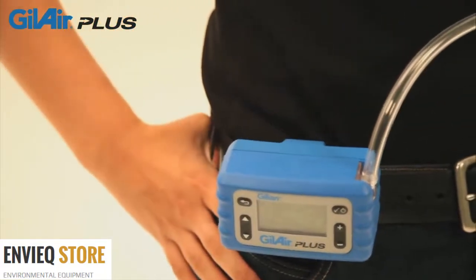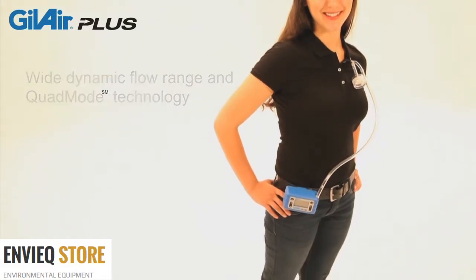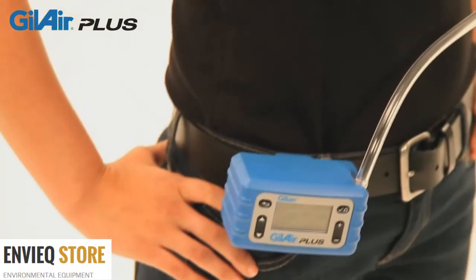GilAir Plus has the widest dynamic flow range of any personal air sampling pump. It is the first pump to offer quad-mode air sampling technology that enables constant flow of 20 to 5,000 cc per minute and constant pressure sampling in low and high flow modes without using external adapters.